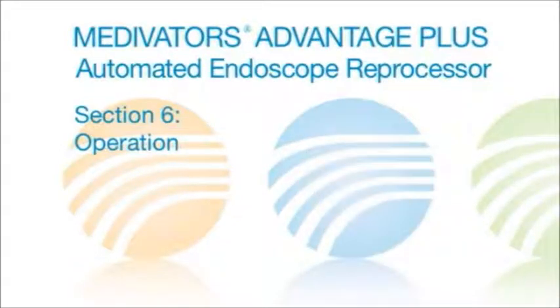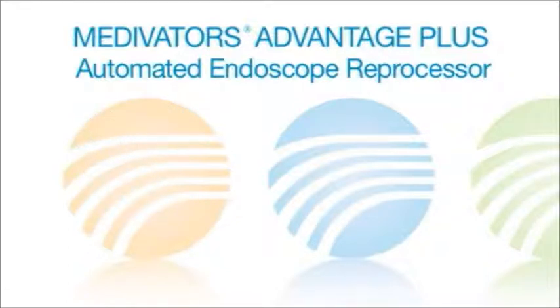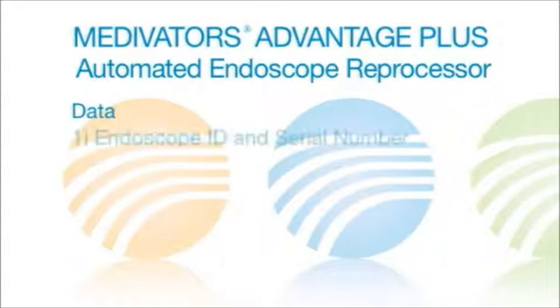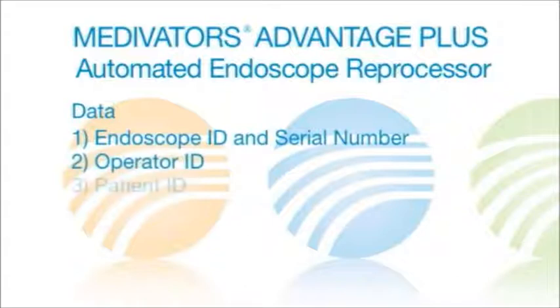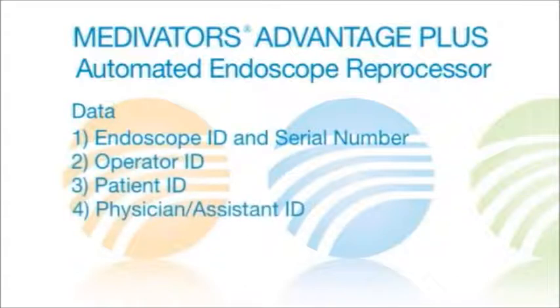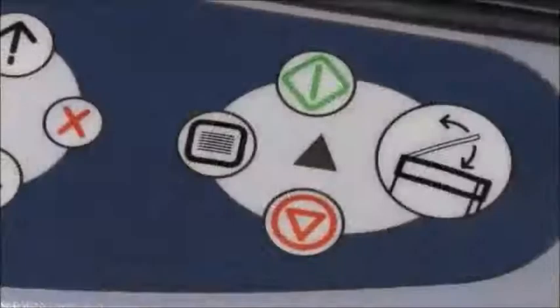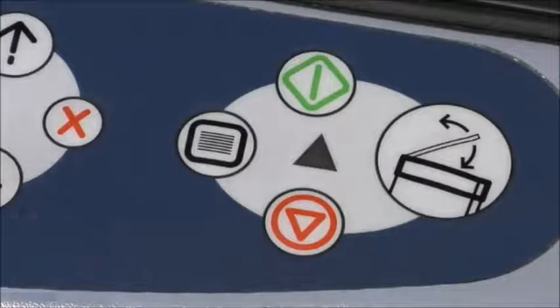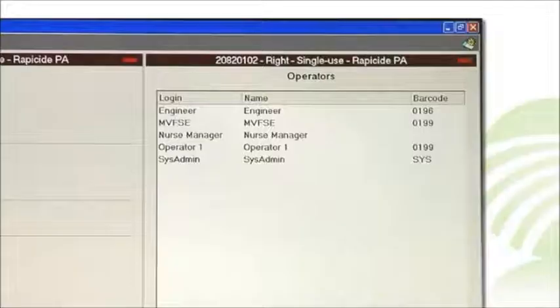Most owners take advantage of the ability of the Advantage Plus to store data each reprocessing cycle. The information recorded can be the endoscope ID and serial number, operator ID, patient ID, and physician ID. The information requested will vary depending on how the Advantage Plus was set up. After the endoscope has been loaded into the basin, press the menu button on the basin side you would like to start. If you place the endoscope in the right basin, press the menu button on the right side.